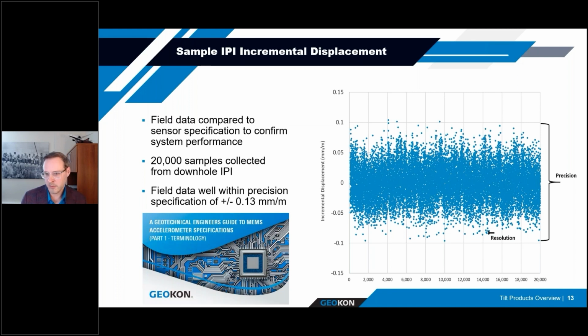So what we would want to see with this type of test is 99% of the data should fall within that plus or minus 0.13 millimeter per meter, and you can see we're well within that range. The other thing that we can show here is resolution, and I've shown in the bottom the resolution value. So this is the smallest change in angle that you can detect. So you can see here when you're talking about the resolution value, it's really meaningless when you have a precision value here that is much, much larger.